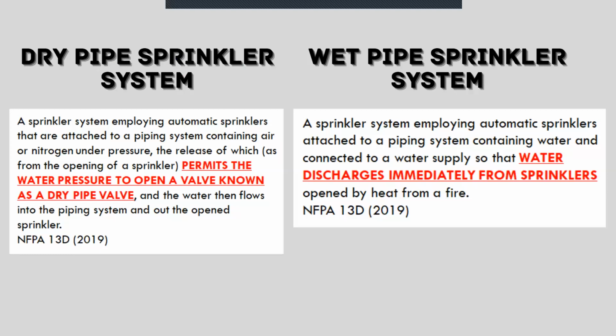Ano ang dry pipe system? It is a sprinkler system employing automatic sprinklers that are attached sa isang piping system, pero it contains air or nitrogen under pressure. Ang contained air na ito ay released lamang kapag may sprinkler head na pumutok, saka lang papasok ang water, i-a-actuate ang valve na tinatawag na dry pipe valve. Kaya pagka pumutok lamang ang sprinkler head, may time bago fully lumabas ang water doon sa sprinkler head. Yun yung dry pipe sprinkler system.